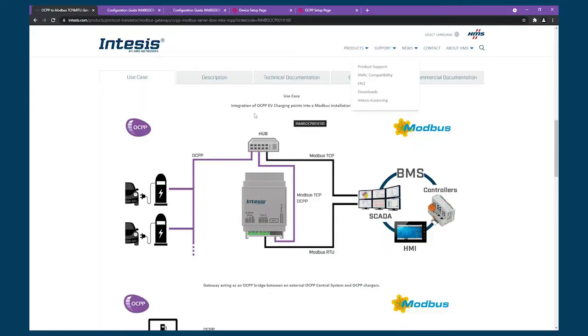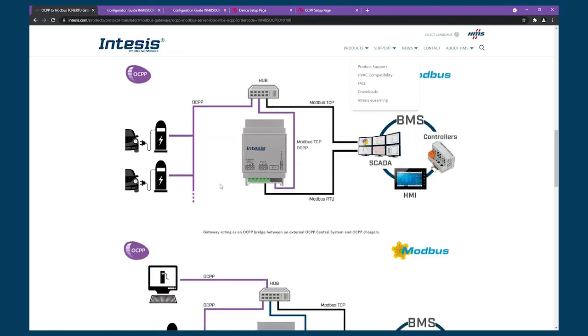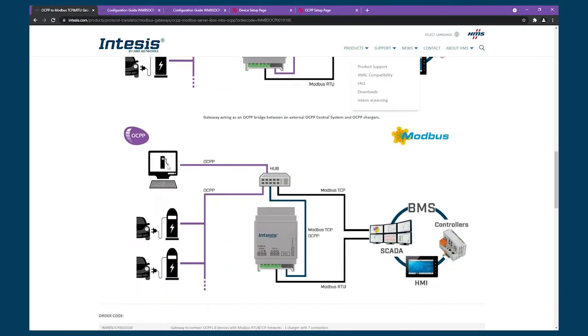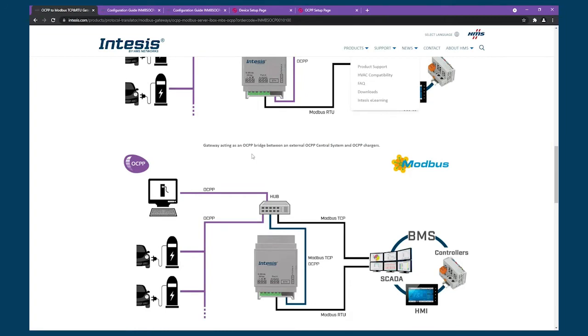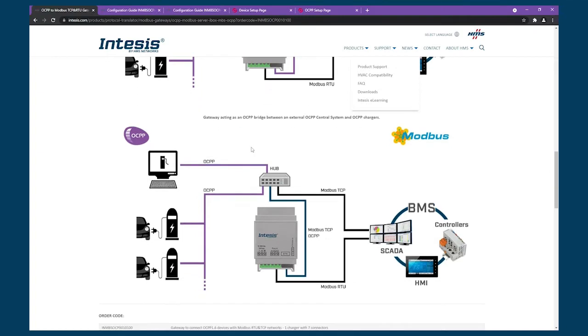This gateway allows you to integrate electric vehicle charging points based in OCPP 1.6 with any Modbus RTU or TCP controller or connect the charger to an external OCPP central system and monitor them via Modbus. The OCPP gateway is slightly different to the rest of our portfolio as it requires that you actively answer to the charger request and you will have to set multiple registers at the time for this.